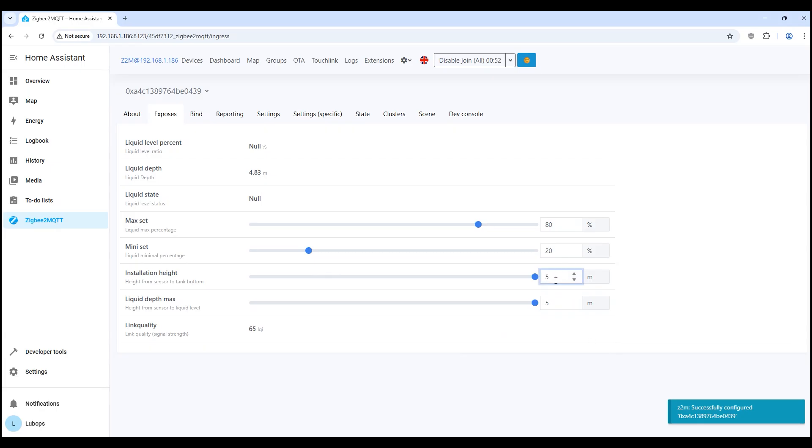Configurable parameters: Max set 80%, maximum level after which you can signal full tank. Mini set 20%, minimum level at which it is already worth giving the signal time to top up. These are exactly the percentages of the specified range that need to be set lower. For now they are working idle. As soon as we determine the installation height and max depth, everything will fall into place. Installation height 5 meters. This is the height from the sensor to the bottom of the tank. You have it set to 5 meters. It matches the depth, which means that the tank is most likely just to the brim. Liquid depth max 5 meters. This is the maximum level to which there can be water. That is, full tank is also considered 5 meters. Logical. Based on these two values, the liquid level percent and the liquid state status will then be calculated.